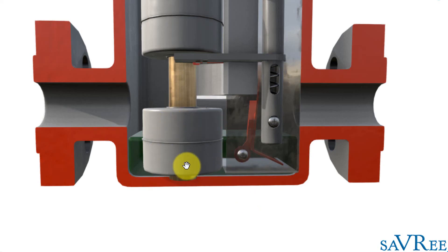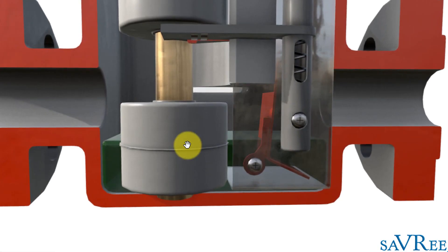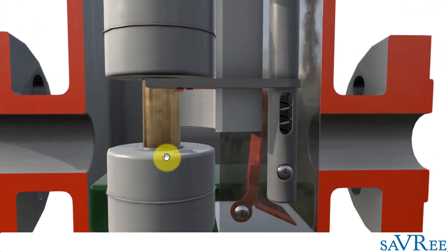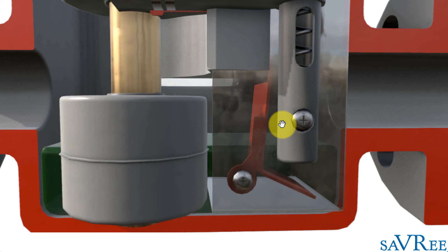So what we'll do, we'll have this second lower float here and that will set off an alarm. In fact, it will actually set off an alarm and shutdown. So this is another shutdown trip. Remember the baffle plate pushing the lower float down was one shutdown. And now we've got two floats dropping together, the top and the bottom. That's another shutdown. So this is a shutdown scenario and it means we've got low insulating liquid in the transformer. If that happens, then we have to take action immediately and find out what's going on.